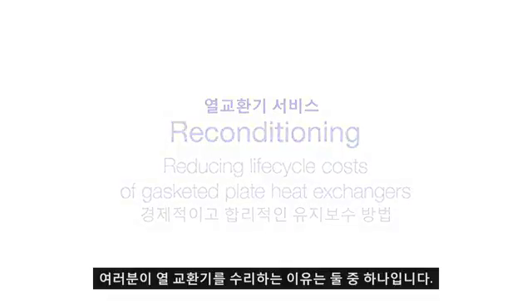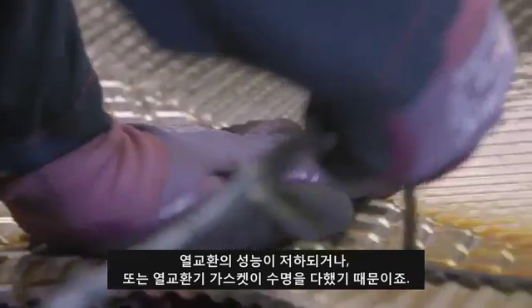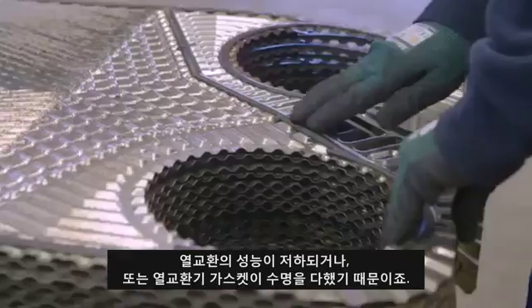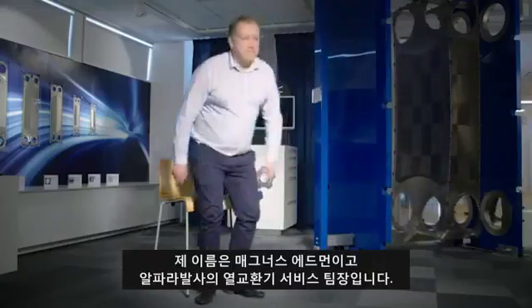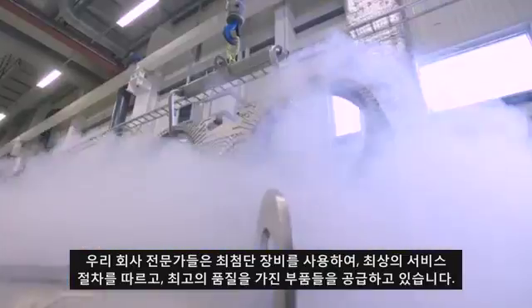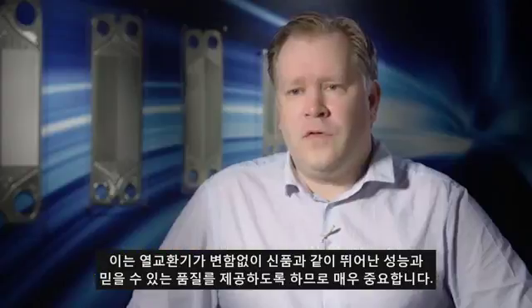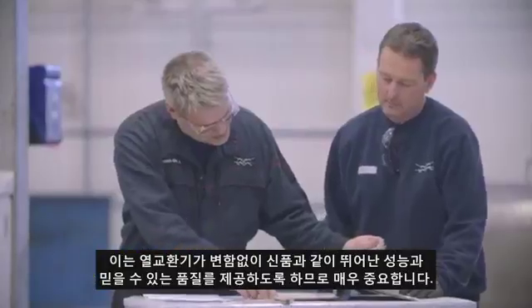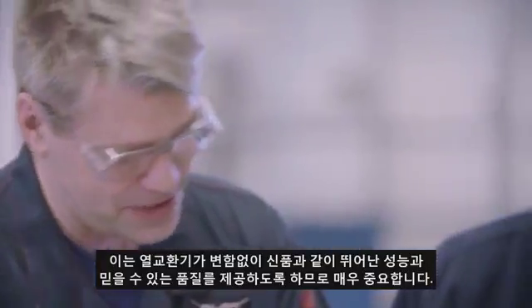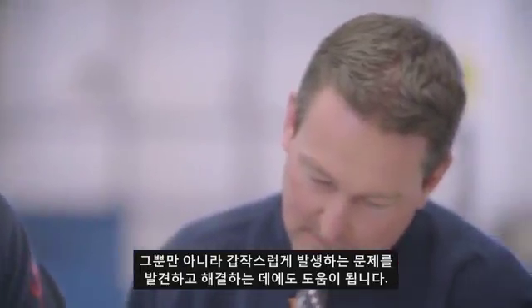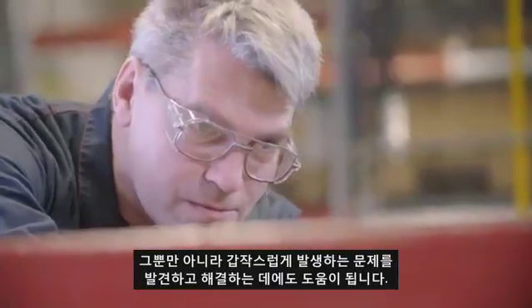You recondition a heat exchanger for one out of two reasons. One, it's lost performance, and the other one is because the gaskets between the plates are approaching end of life. My name is Magnus Edmain, and I'm head of service for gasketed plate heat exchangers at Alfa Laval. Our skilled professionals use state-of-the-art equipment, state-of-the-art service procedures, and the highest quality spare parts. And that's important because that gives you performance as good as new, it gives you reliability as good as new, but it also gives you an opportunity to learn about emerging problems and also what to do about them.